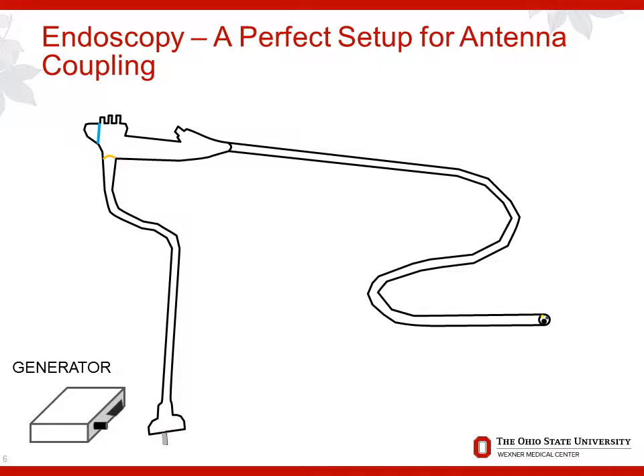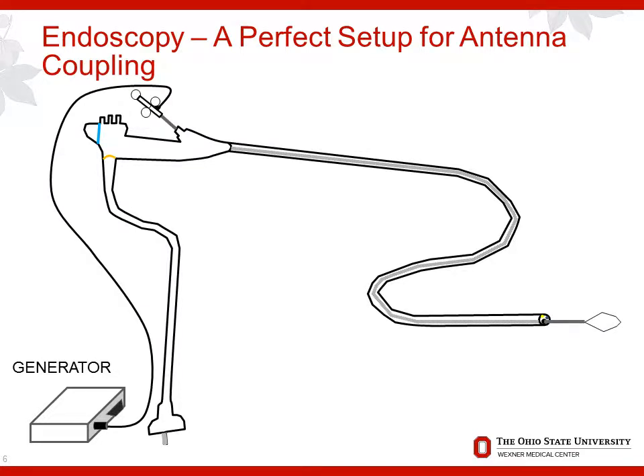Unfortunately, the very design of endoscopic equipment is a perfect setup for energy coupling. The active electrode is placed through the working channel and is always in close proximity to the endoscope itself. The working channel and camera cable are insulated against the direct transfer of energy. However, antenna coupling does not require direct contact and only requires close proximity and parallel alignment for significant energy transfer.